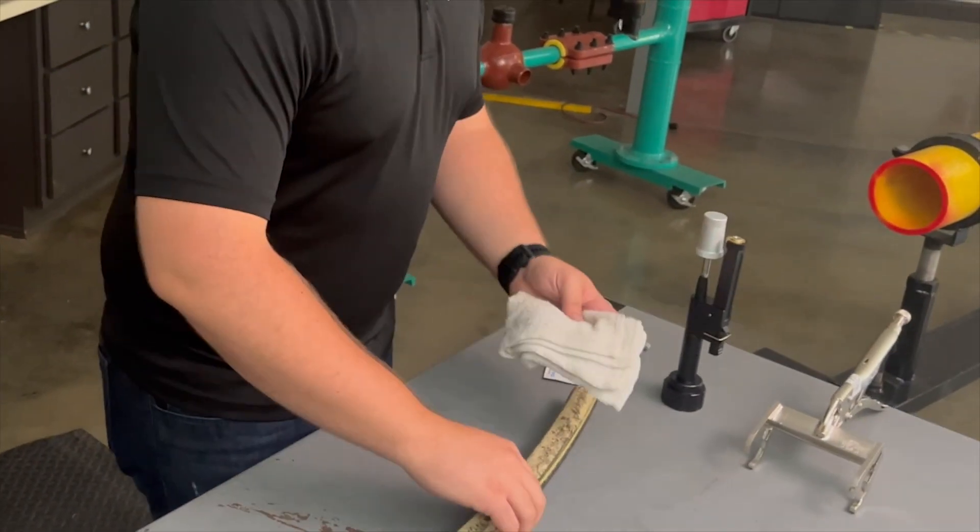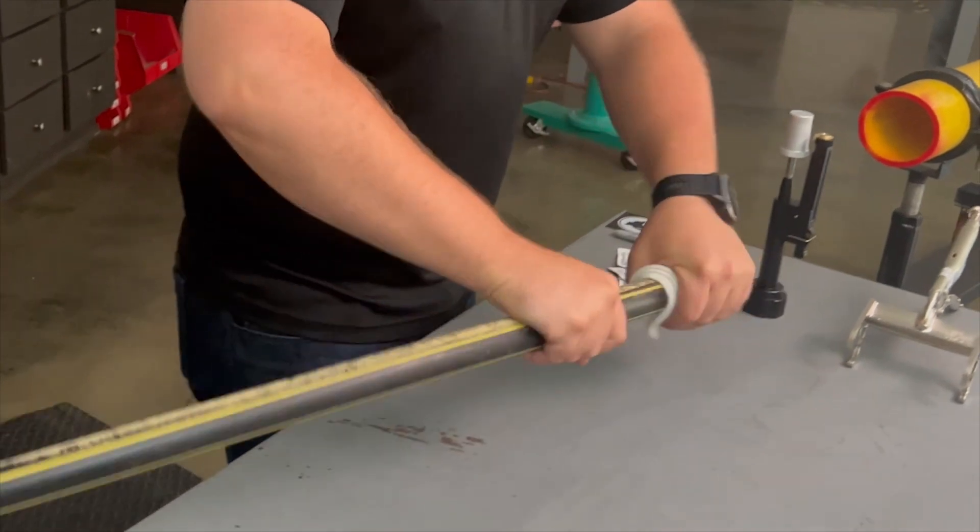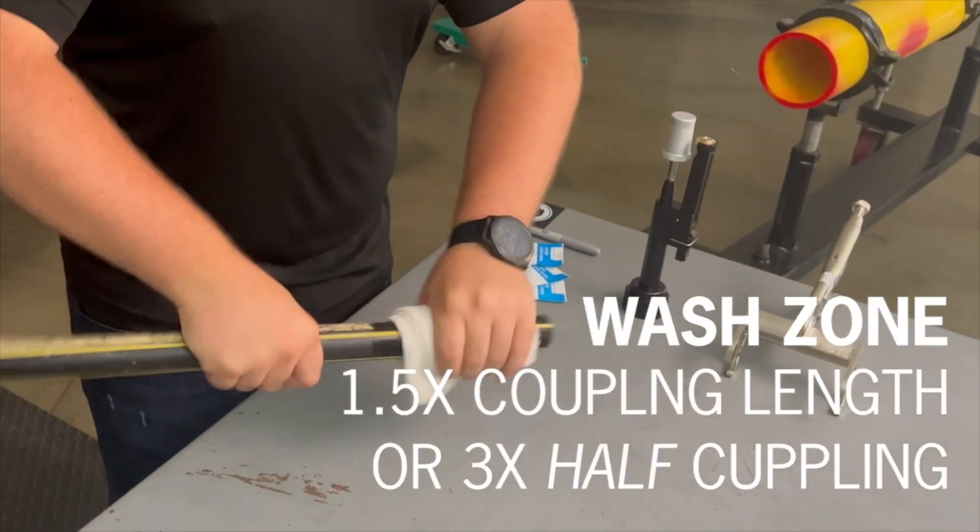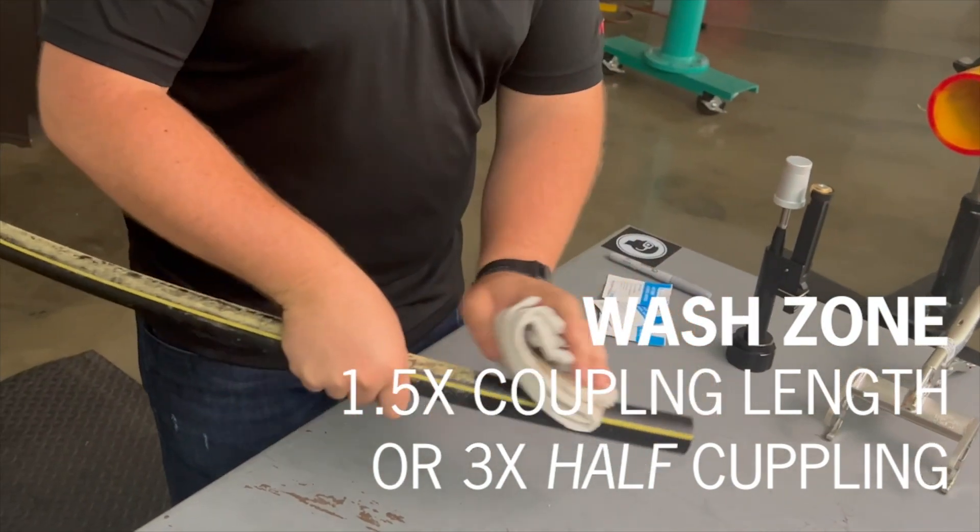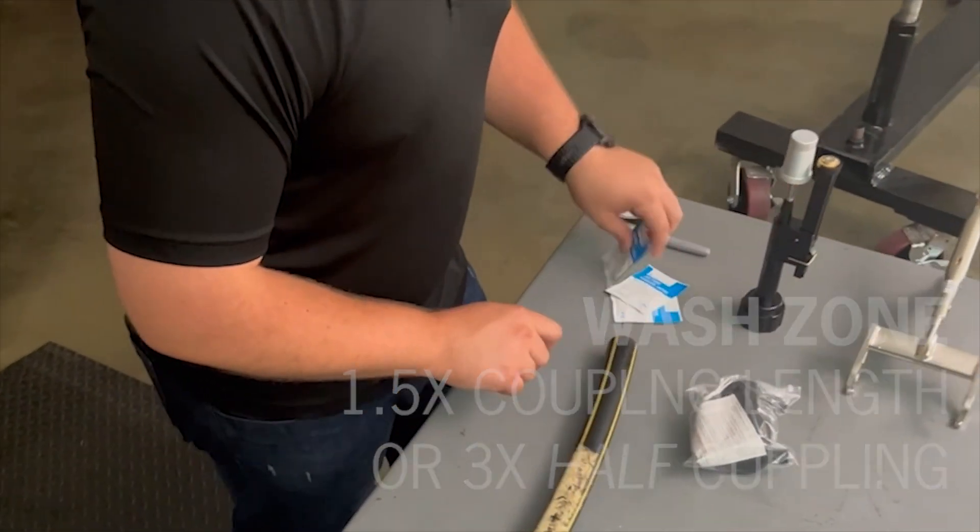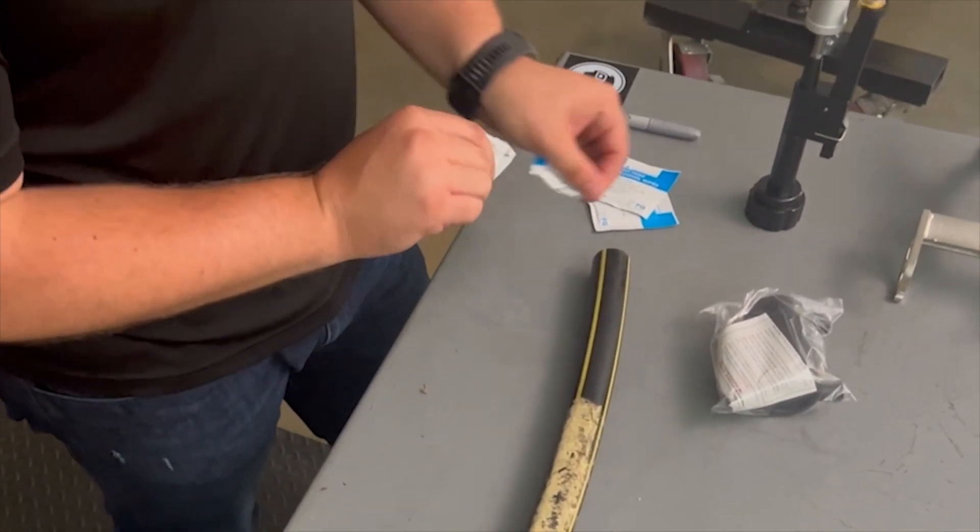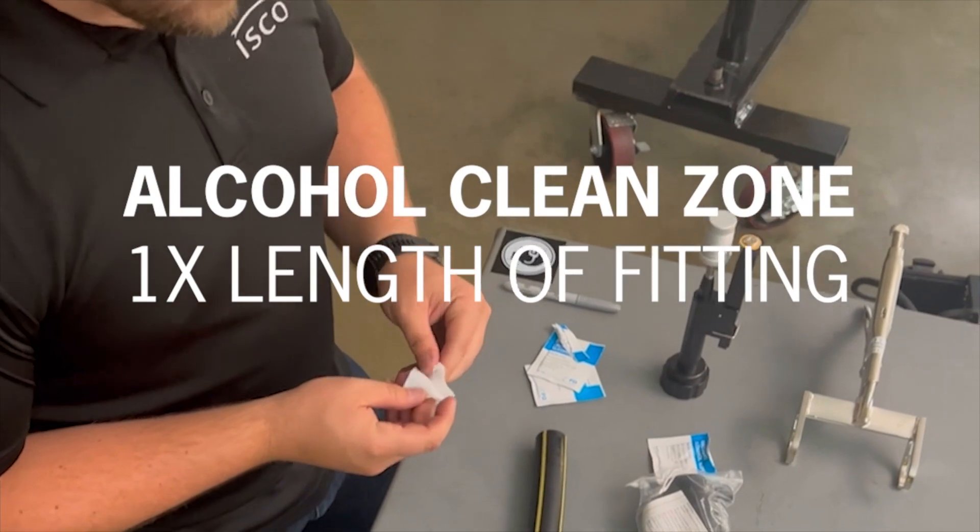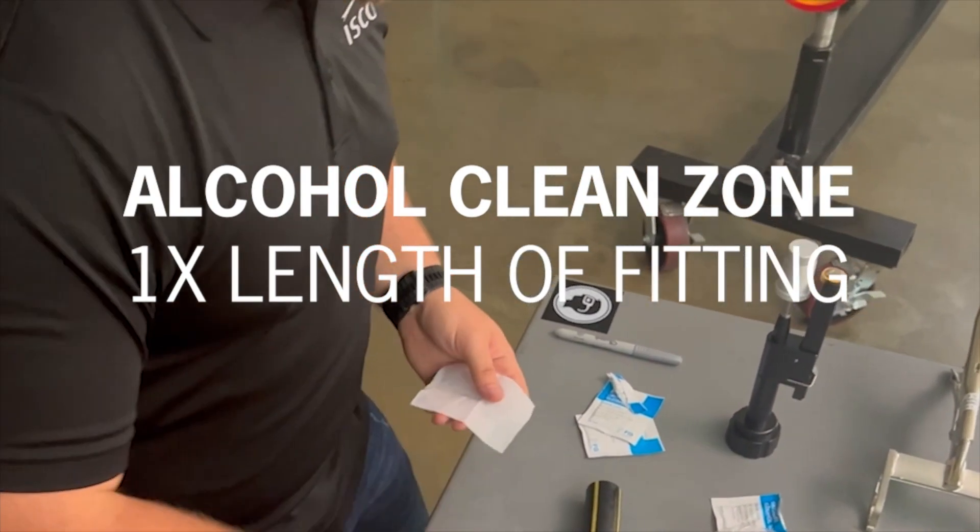Now, prepare the pipe to be fused to the outlet. Using a damp cloth, remove any loose contaminants from the pipe. The length of water washed area should be one and a half times the total coupling length, or three times half the coupling length. Next, use an alcohol wipe to clean the pipe within the water wash area one time the length of the fitting from the end of the pipe.